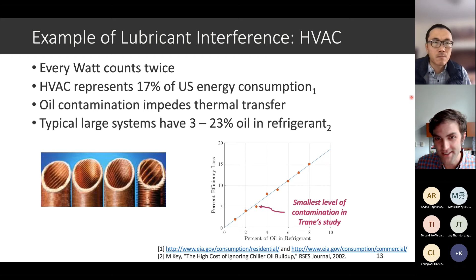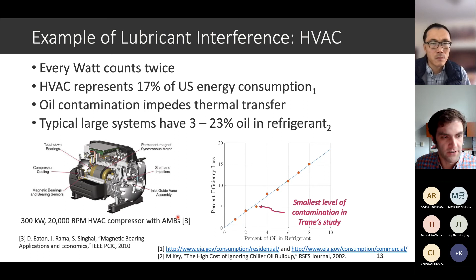Trane went out and surveyed their commercial installations and found that the smallest level of contamination in any of the buildings that they studied was 3%, leading to a 5% reduction in efficiency. The largest was 23%, which is off this chart, right? So you can see that this is a major problem. And not surprisingly, the large HVAC OEMs have responded, and all of them now have a product line that uses active magnetic bearings in place of journal bearings. They call them oil-free chillers. And Daikin, Trane, all of the companies have a product line around this.